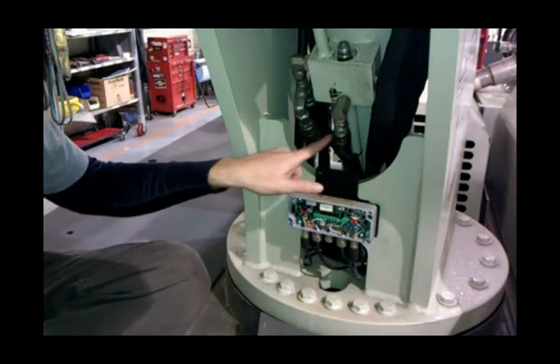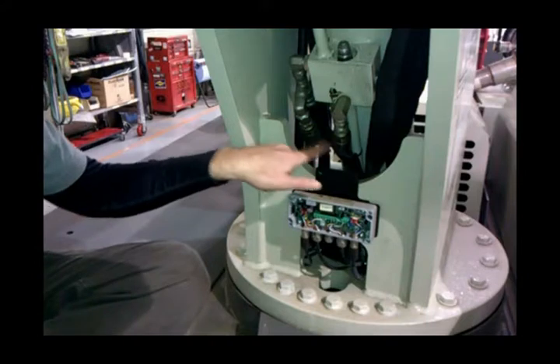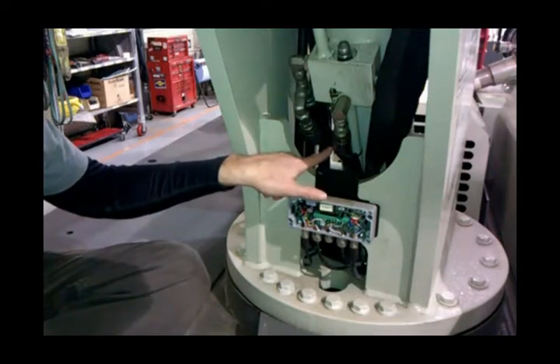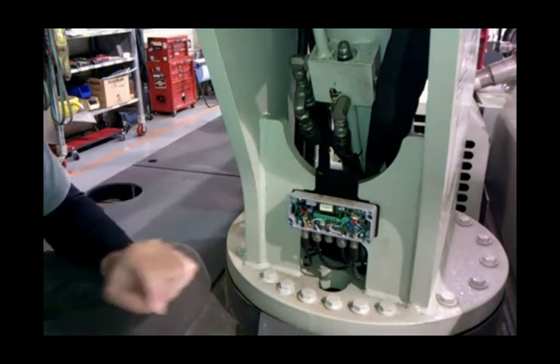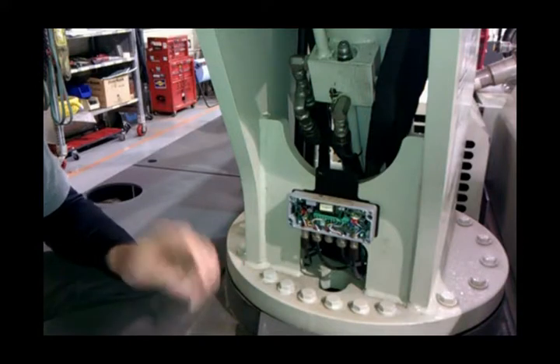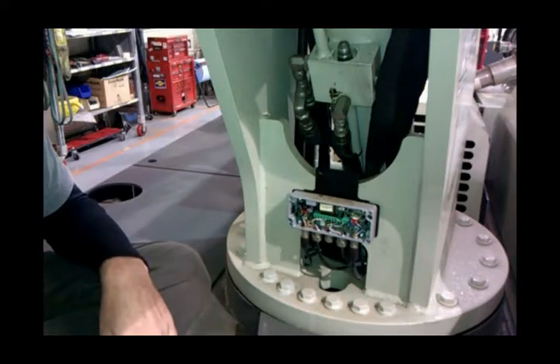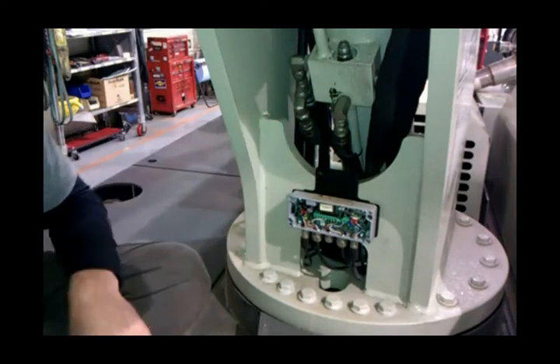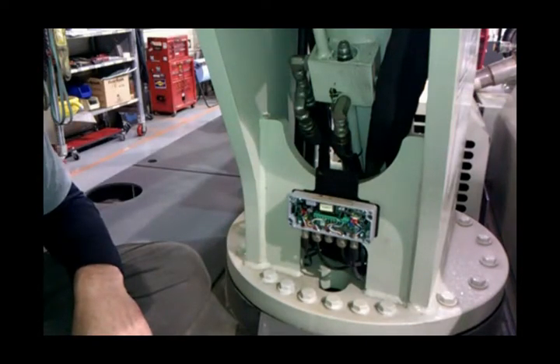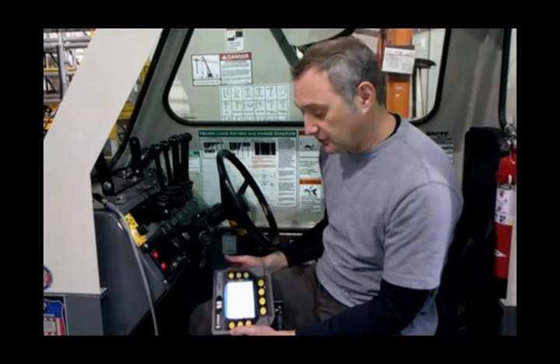The other thing you need to know is these two transducers are specific. Normally, there's a label on them indicating which one is the bore and which one is the rod. If it doesn't have a label on it, you're going to have to revert back to either your own knowledge on the system or a hydraulic data which shows you which port is for the rod and which port is for the bore. So we're going to go ahead and calibrate the pressure transducer.